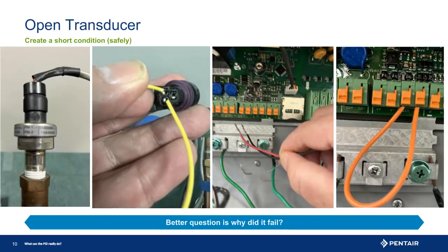Now, should it not show short, disconnect the transducer wire from the drive input and place a jumper as shown here. Again, upon starting the drive and running, the pressure should show maximum pressure and then fault out to transducer short. If this is the case, replace the transducer wire. Now, if this test still shows as transducer open, the issue is most likely in the drive. And remember, do not replace the transducer in an environment that will allow it to fail again, as discussed earlier.